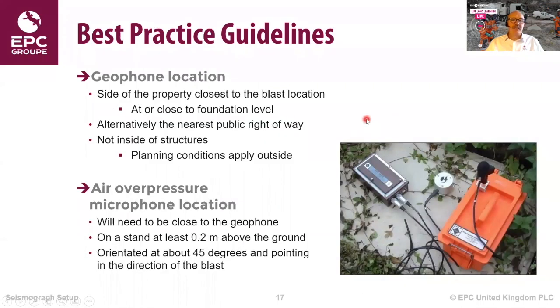So where do we locate our geophone? Well, generally, best practice would be to locate it close to the property at foundation level on the side of the property closest to the blast. Now, sometimes you can't get permission to monitor at someone's property or go on their land, so you may need to then go to the nearest public right of way and monitor there.